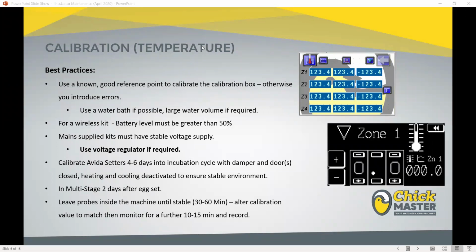If you are using one of the older kits, which is mains supplied, and you're in an area of the world where the incoming voltage isn't necessarily stable, it's highly recommended that a voltage regulator is used, for exactly the same reason that the temperature readings are impacted by the voltage of the equipment that it's been supplied with. Once you know that your calibration kit is safe and secure, and it's going to give you known good readings, then you can start putting it into the incubator.